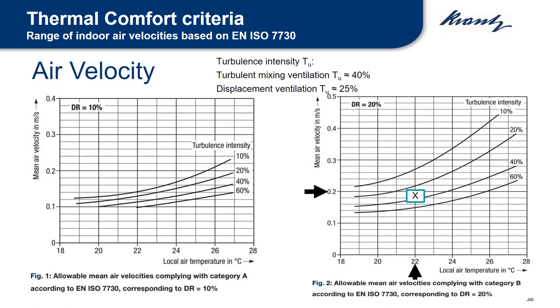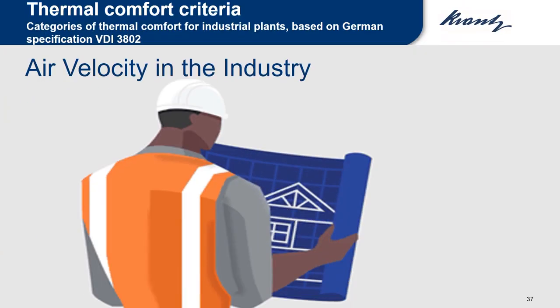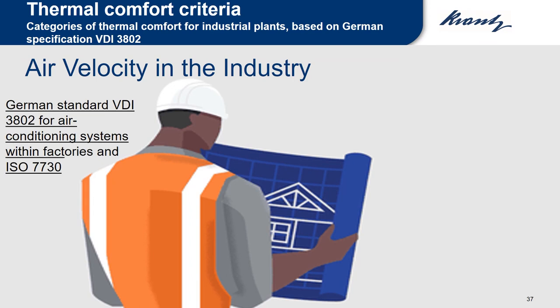These values are important for the choice of the different air distribution systems. It is important to note, for example, that for turbulent flow systems the reference is 40% and for displacement ventilation 25% degree of turbulence. Therefore, higher air velocities are allowed for displacement ventilation. Allowable indoor air velocities in industrial plants are specified, for instance, in the German standard VDI 3802, air conditioning systems for factories, and also in the ISO 7730.